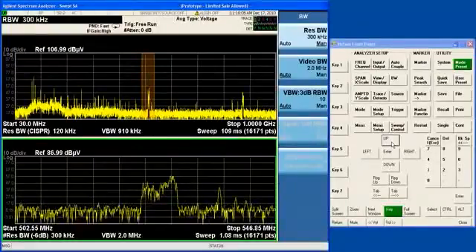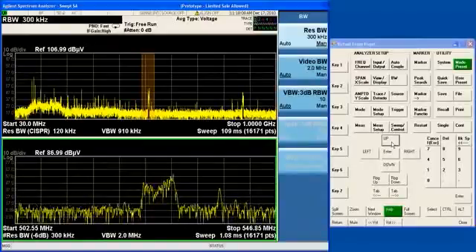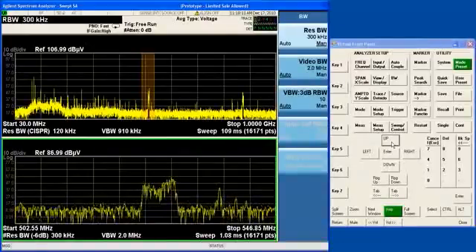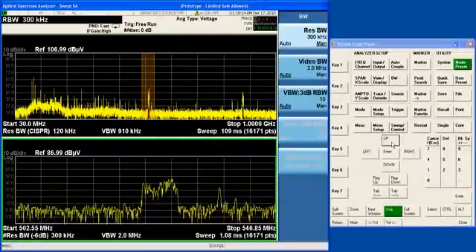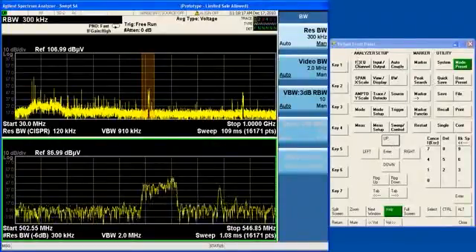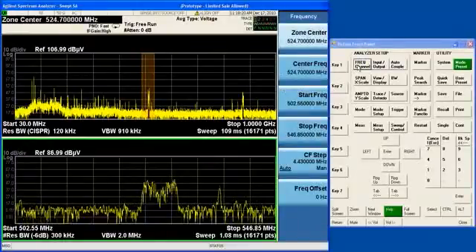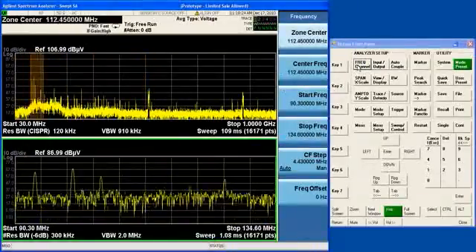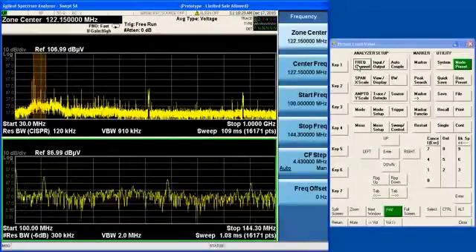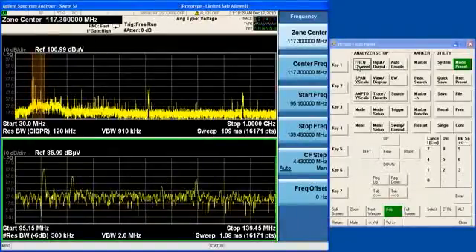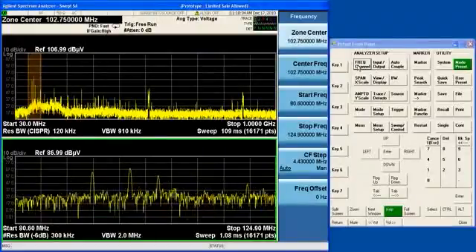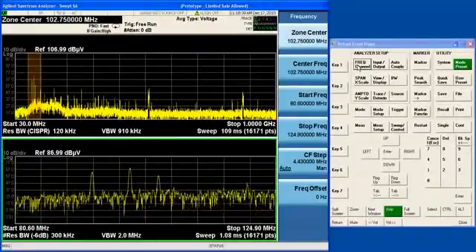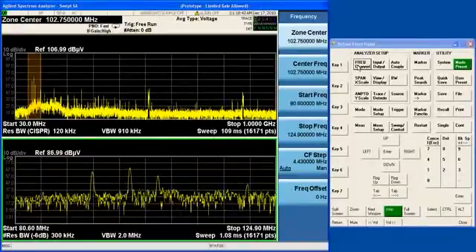Okay, so the ability to zoom in on signals and measure them with parameters that are different from those in the upper window is really quite powerful, and particularly when you're making EMI measurements. For example, I can roll down here to the FM band, and I can see the individual FM stations. I can go to one of them and demodulate it or look at it more closely while retaining the original scan of the entire frequency range.